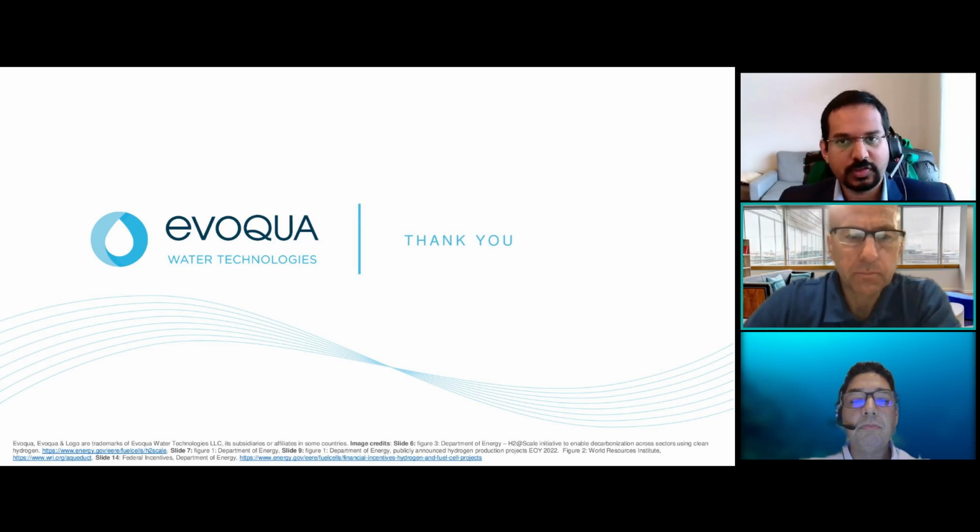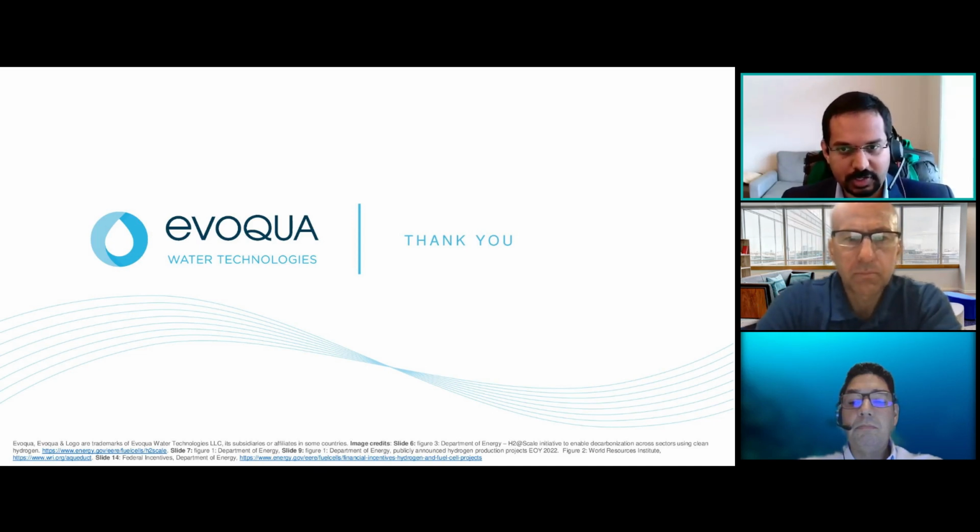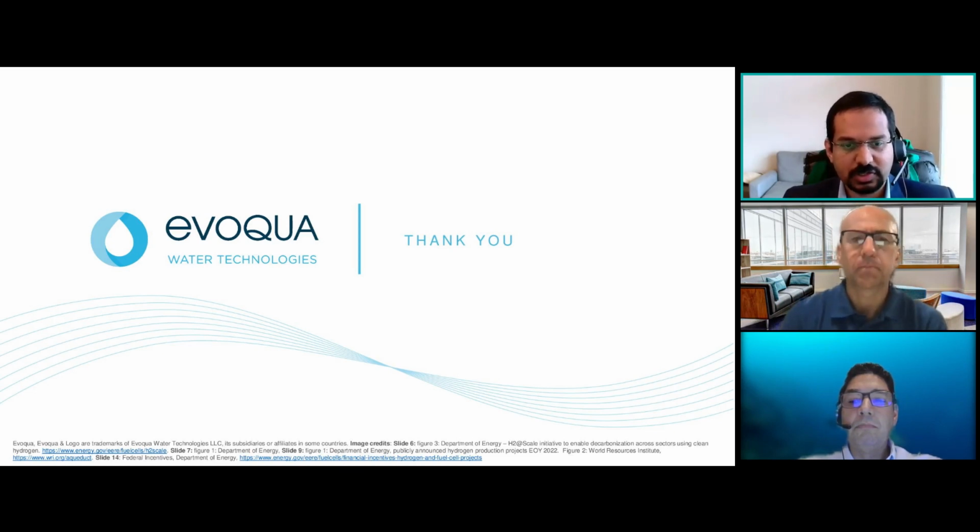Yeah. So that's a good question. It's not just the technology. There's also a pretty strong operational component to it as well. In some of these technologies, biofouling is something that needs to be prevented a lot. So it goes down also into the piping design, how many bends you have or you don't have, and how close the electrolyzer is to the makeup water source, and how frequently you sanitize the lines. There's a significant operational component to it as well that we have figured out in decades of semiconductor water treatment, where the water treatment standards are in some cases even more stringent. So it's not just the capital, but how you use the capital with trained personnel and operations and maintenance procedures.